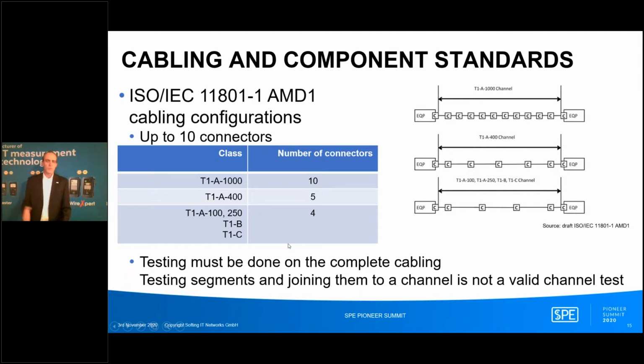From a testing point of view, that's why I bring this up again, you always have to test the complete assembly, the whole thing basically, like here in this example, the T1A400 channel. You cannot take one segment of the cable, test that, take the next segment, test that, and then join everything together and say this will work. That's not how these tests work. The definition says you always have to test the whole assembly.